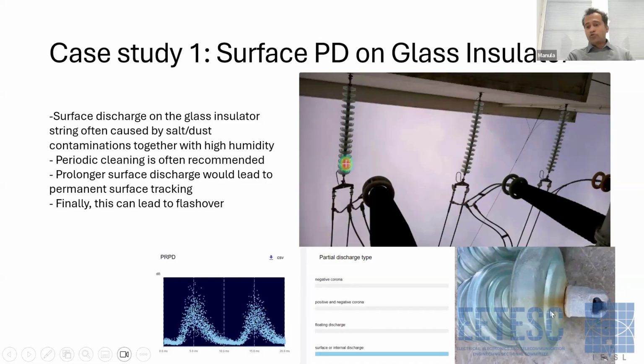So over time that would lead to flashover as well. So therefore it is very much important to detect this kind of surface partial discharges at their beginning or during the routine inspections and take remedial actions. For example, we can wash these insulator strings so that whatever the contamination is removed and surface discharges would not be occurring over a prolonged time.